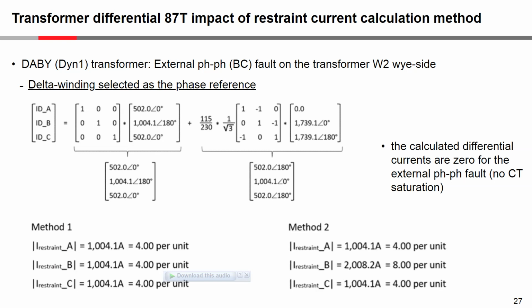If we look at method 2, this would be the 502 plus 502 for phase A, the 1,004.1 plus 1,004.1 for phase B, and similarly for phase C. And so you can see that this is how the compensated currents, or the restraint current, would be calculated if we use method 2.